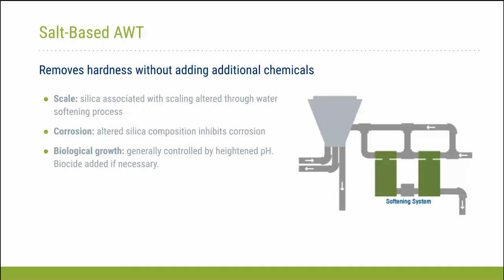Essentially what we saw in the results for this system is close to 100% elimination of blowdown. The softening system that you see on the right does go through a regeneration process, and depending on how much water is being run through the system, so in Colorado, for example, depending on if it's the middle of the summer or the swing seasons, that regeneration process changes a little bit. In the middle of the summer, 2 to 3 times per week, about 70 gallons of water is discharged down the blowdown, and then in the fall and spring, it's about once per week. But again, there are no chemicals used in this system, and the softening system is taking care of everything. Okay, next slide.